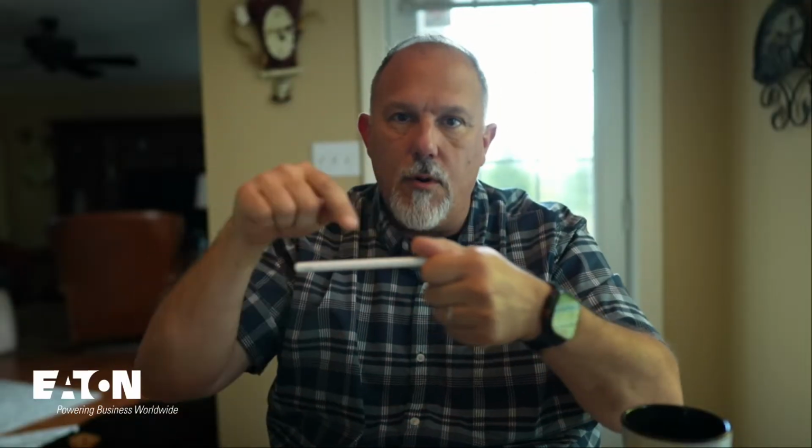Then I have to worry about my equipment. If my equipment is rated for 75 degrees C or 60 degrees C for that size conductor landed on that termination, I can't pull more than whatever is in the appropriate column of 310.16 through that termination. All of that is done in 430. Remember, 240 gave up purview.